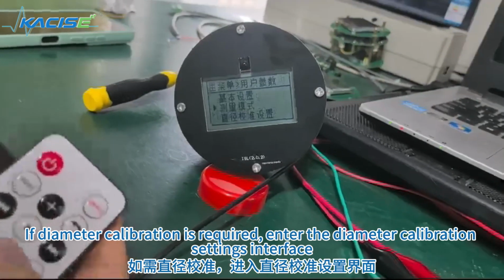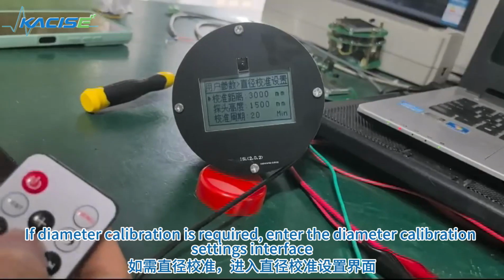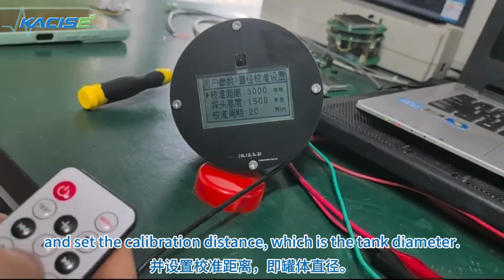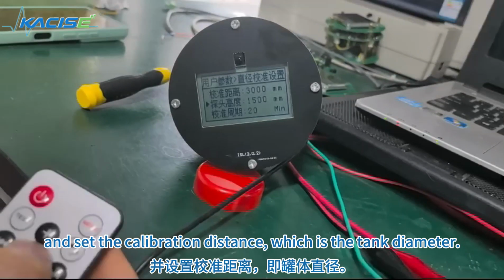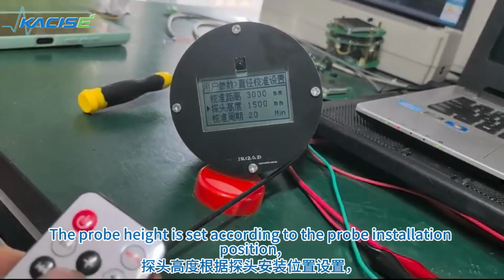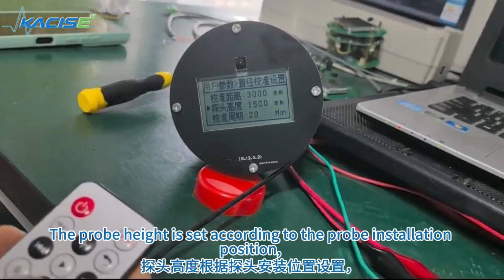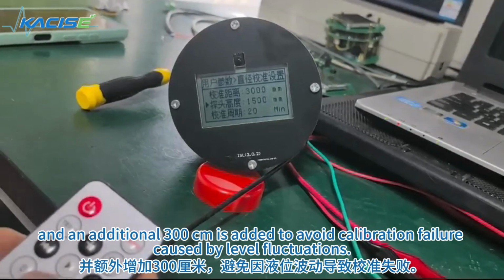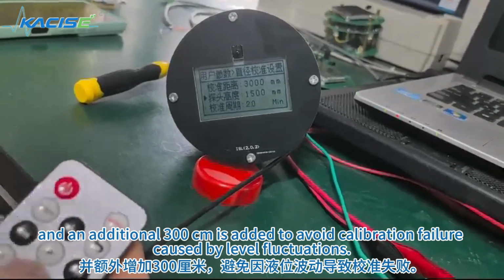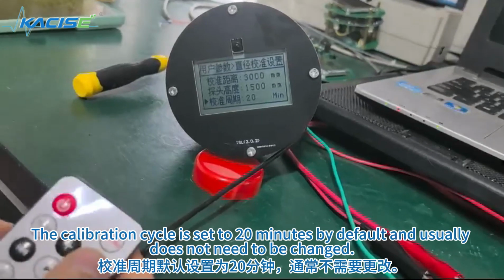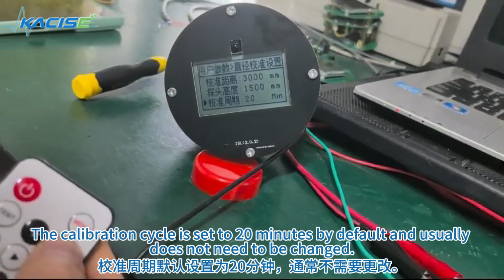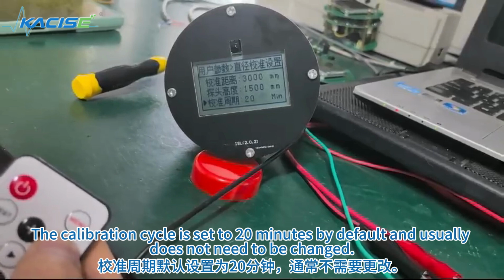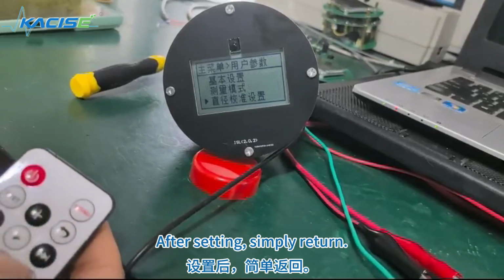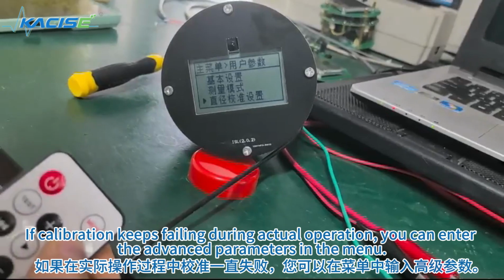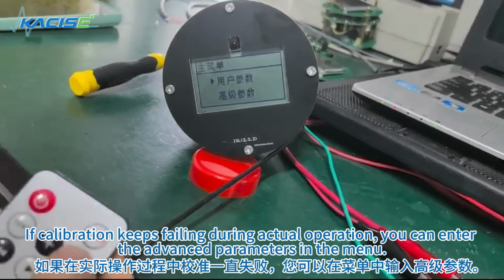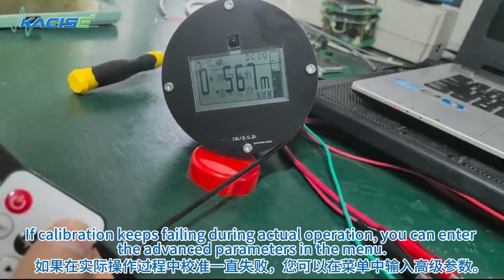If diameter calibration is required, enter the diameter calibration settings interface and set the calibration distance, which is the tank diameter. The probe height is set according to the probe installation position, and an additional 300 centimeters is added to avoid calibration failure caused by level fluctuations. The calibration cycle is set to 20 minutes by default, and usually does not need to be changed. After setting, simply return. If calibration keeps failing during actual operation, you can enter the advanced parameters in the menu.